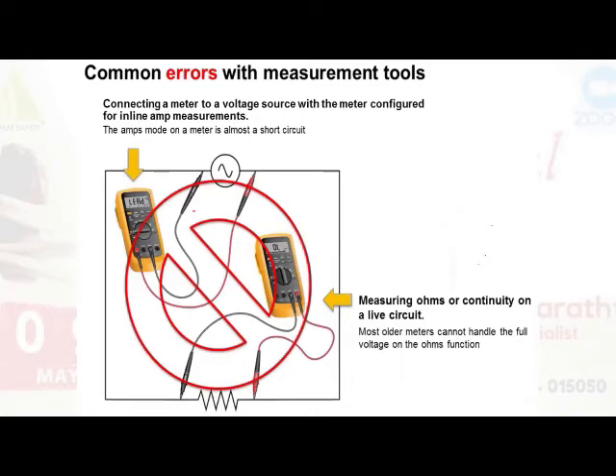The instrument may blow. Also, by keeping it in continuity measurement mode and checking current on a live circuit, again it is considered a short circuit. In both cases, the equipment will blow. If the right equipment is used at the right location with the right fuse, the damage stays with the equipment. But if not, the problem transfers to the person, ending as an electrical shock or arc flash. Hope you got the point.